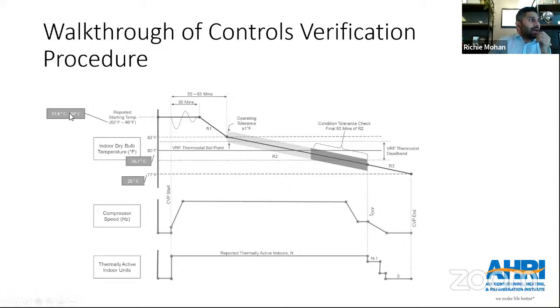That temperature has to be in a certain range, which is going to be 27.8 degrees Celsius to 30 degrees Celsius. So a manufacturer can choose whichever point they want within this range to start off the CVP at. And then we let the test chamber run for a certain period at this temperature condition, such that we can get stabilization.